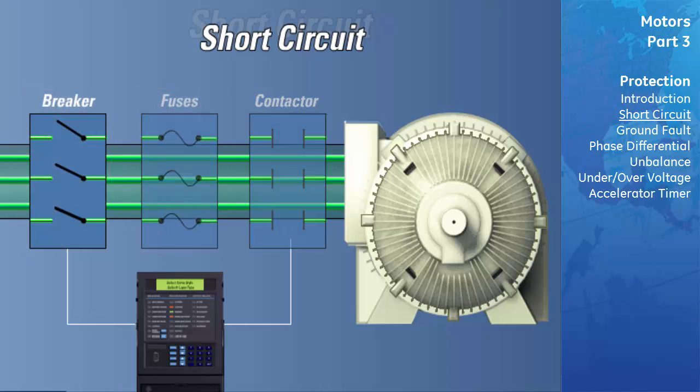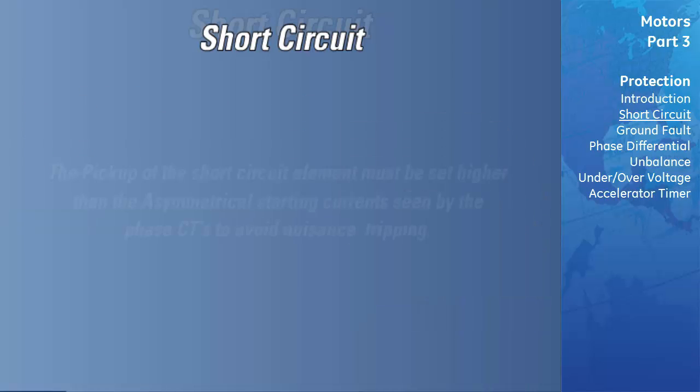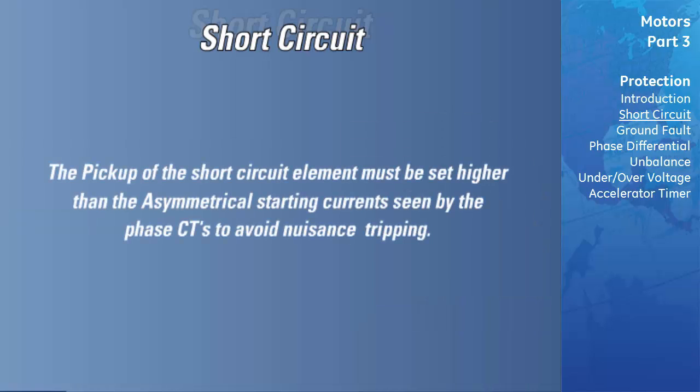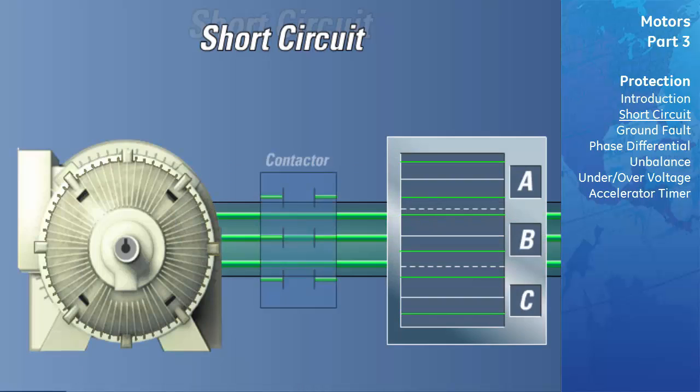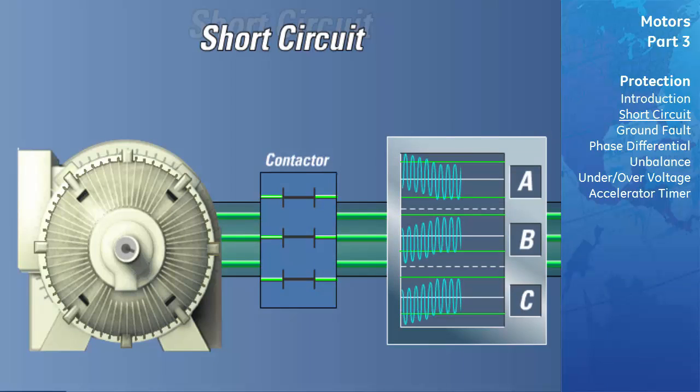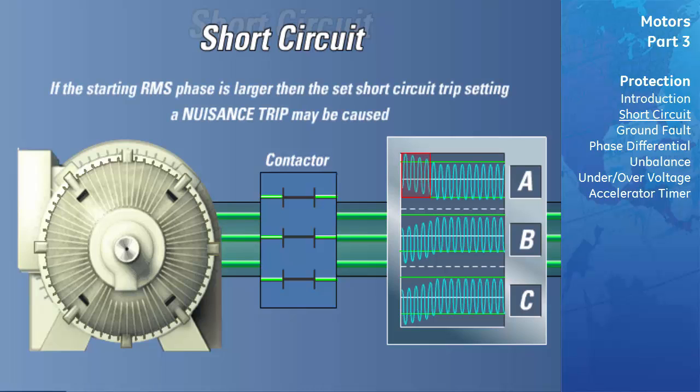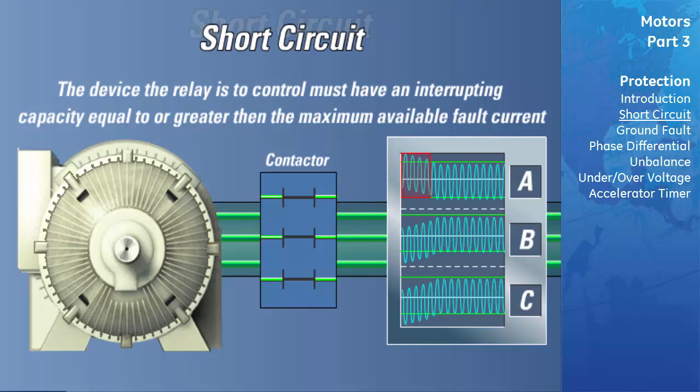These asymmetrical currents may cause one phase to see as much as 1.7 times the normal RMS starting current. As a result, the pickup of the short circuit element must be set higher than the maximum asymmetrical starting currents seen by the phase CTs to avoid nuisance tripping. The rule of thumb is to set the short circuit protection pickup to a value which is at least 1.7 times the maximum expected symmetrical starting current of the motor. This allows the motor to start without nuisance tripping. It is important to note that the device that the relay is to control under such conditions must have an interrupting capacity equal to or greater than the maximum available fault current.